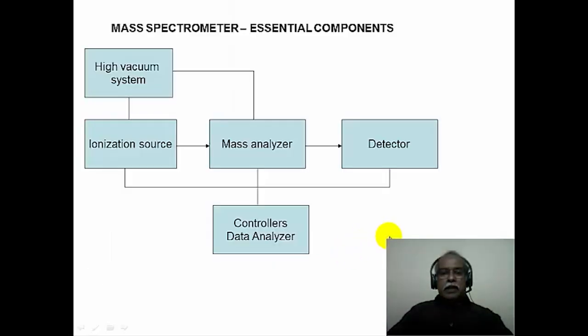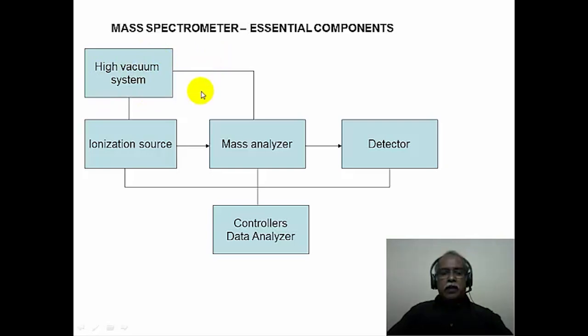A mass spectrometer essentially consists of five components. First, a high vacuum system, because mass spectrometry deals with ions generated in the gas phase. In order to generate molecular ions in the gas phase, high vacuum is essential — we are talking about vacuum of the order of 10⁻⁶ to 10⁻⁹ torr.